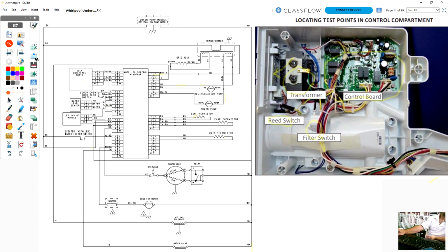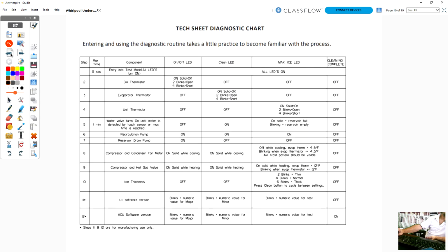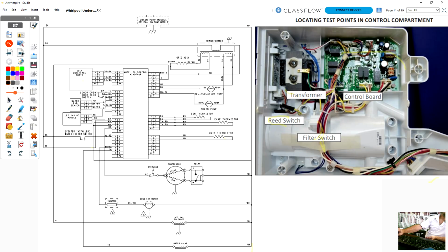So how do we test the components from the board? Let's do a couple of quick tests through diagnostics. I want to check my evaporator thermistor. Now I can ohm it out, but what if it ohms good, but the board is telling me it's bad? What could happen? Anybody have any idea? No? Okay, well, we want to make sure that we're getting our output voltage on the board.